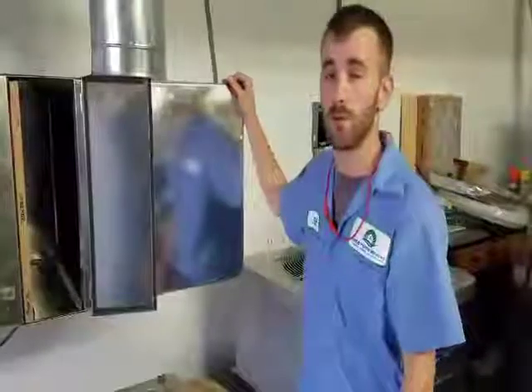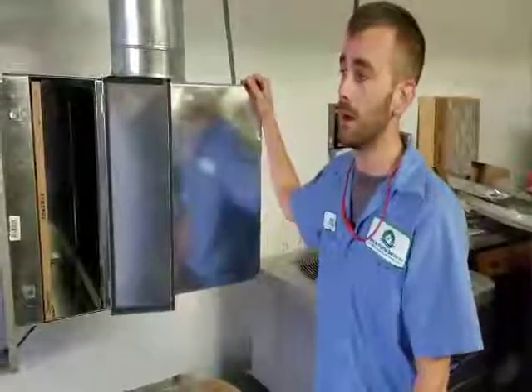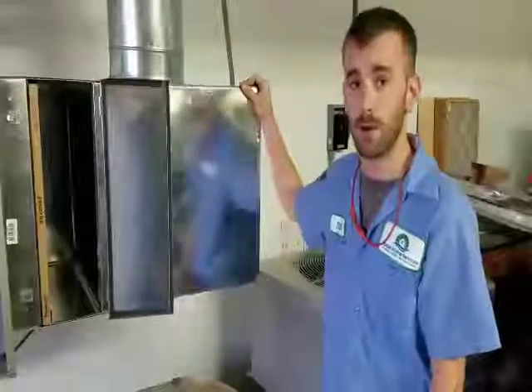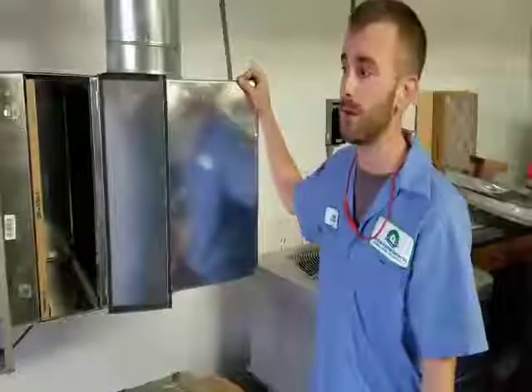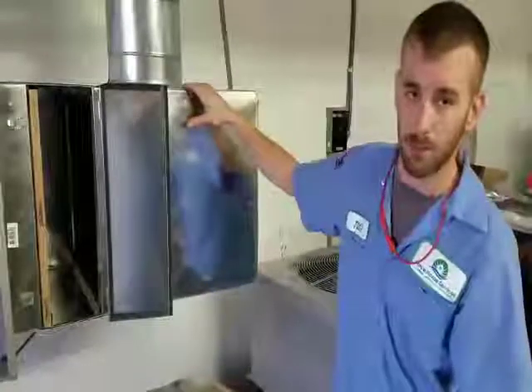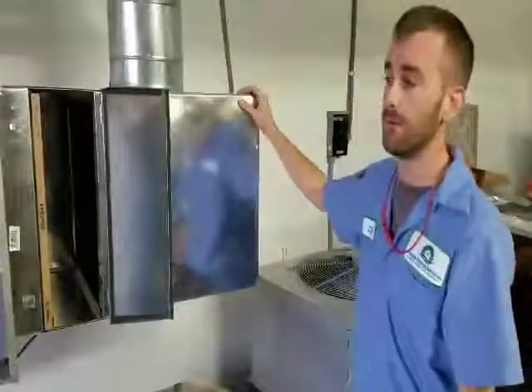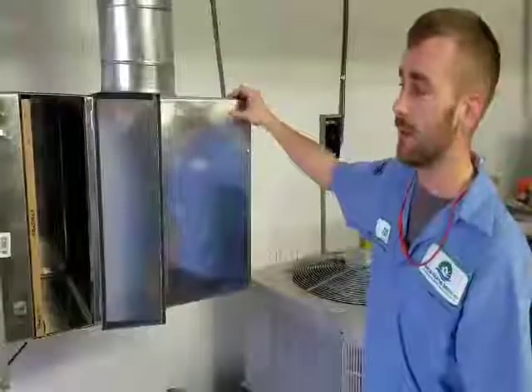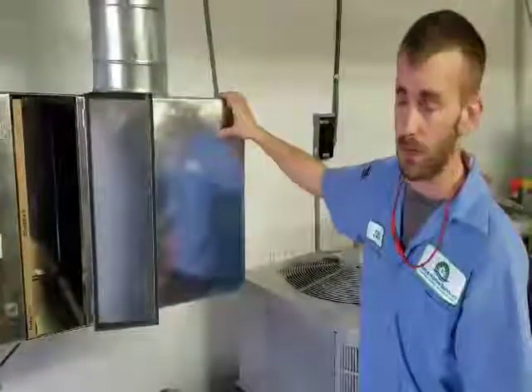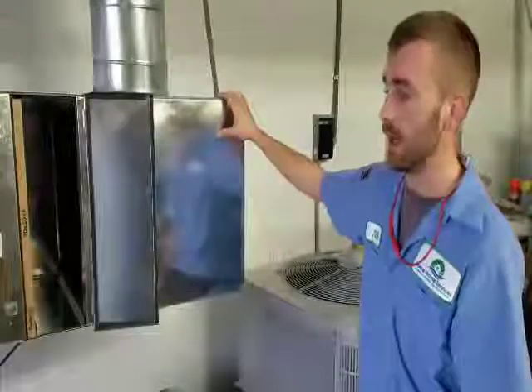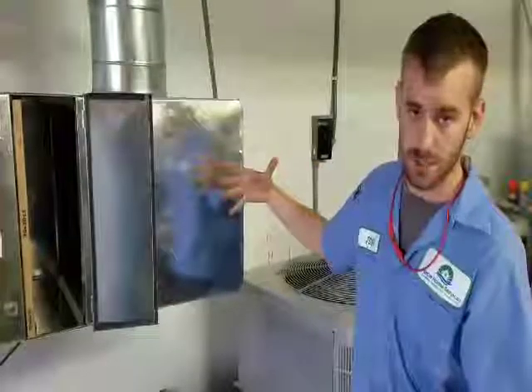Today I want to go over some things that I've been running into a lot. A lot of these systems have high static pressure, and what I mean by high static pressure is your system has high blood pressure. And the reason for this is a lot of these systems are lacking return. They do not have enough return, and the blower has too much restriction.